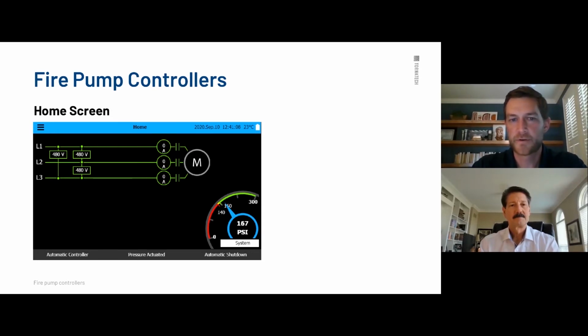You'll see these 3 circles here. That's our ammeter. They say 0A in them. So 0 amps, the motor is not running right now. And you can actually see the motor contacts right next to those, the 3 sets of parallel lines. That represents our motor contacts. They're open right now because the motor is not on. And you can also see that circled M there. That represents our motor. It's gray because it is not on. So there are a lot of indications here showing you that your pump is not running.